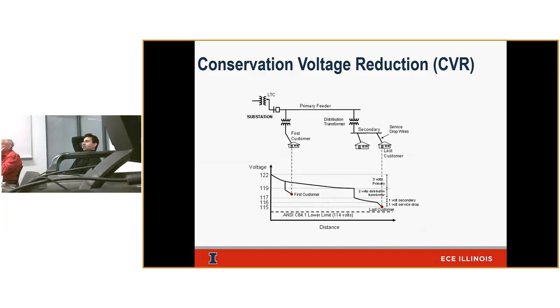Remember, transformers also have a voltage drop across them. The rule of thumb for design engineers is a 2-volt drop across the distribution delivery transformer. Then you have a secondary line and a service drop. The secondary runs single-phase laterals to homes, and the service wire from the distribution transformer to your house also has a voltage drop. So: 2 volts across the transformer, 1 volt for the secondary, 1 volt for the service — that's about a 4-volt drop near the customer.